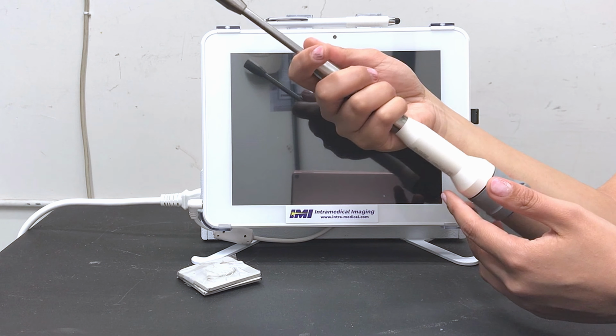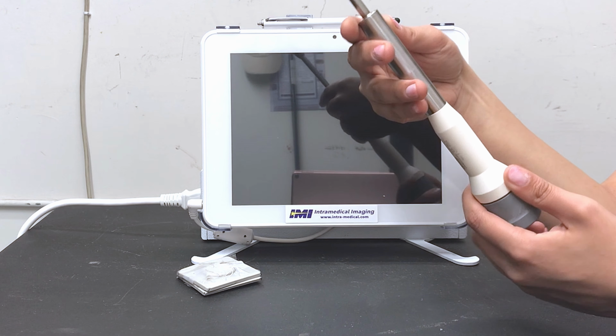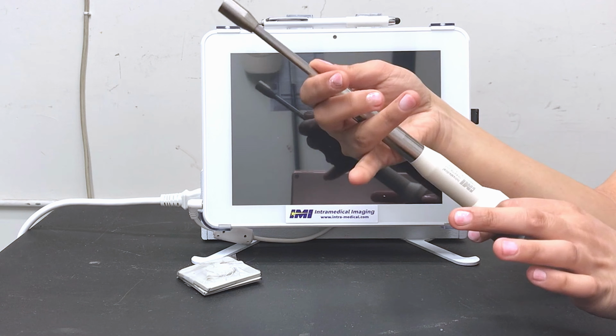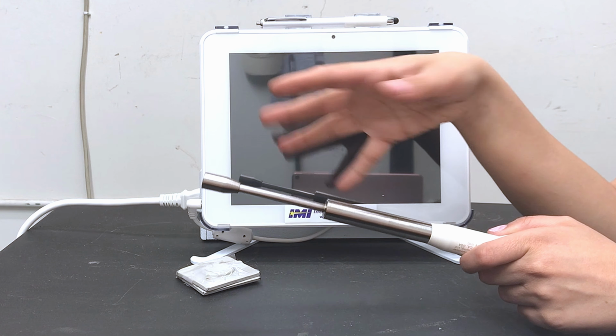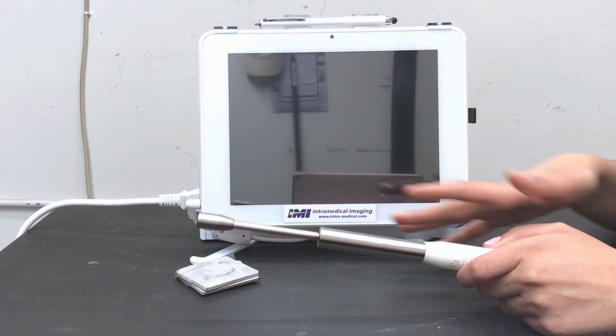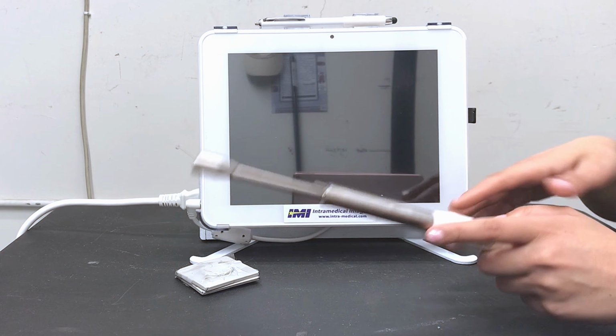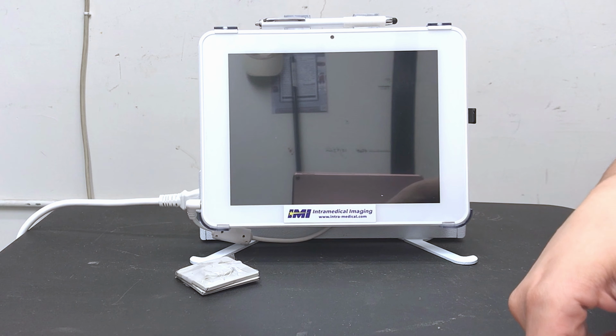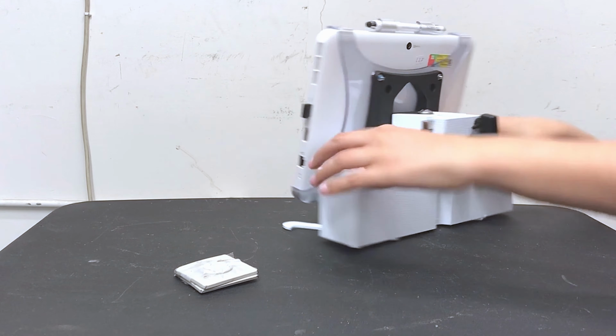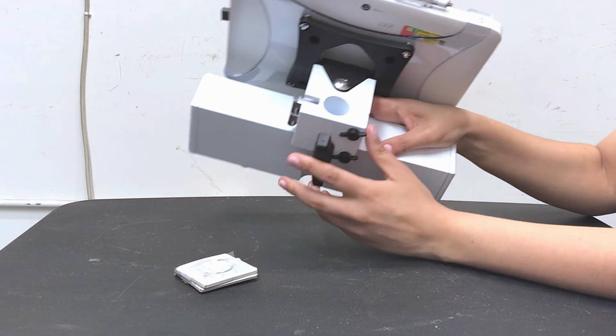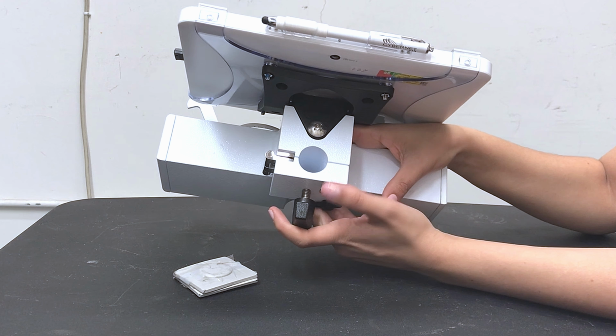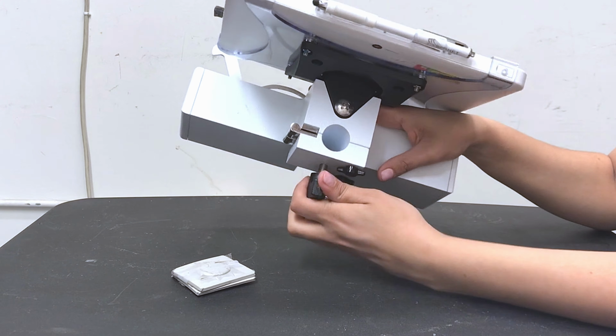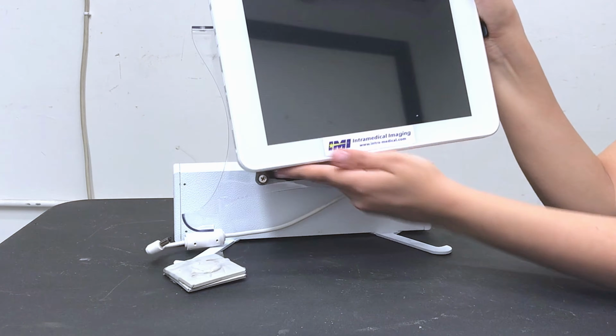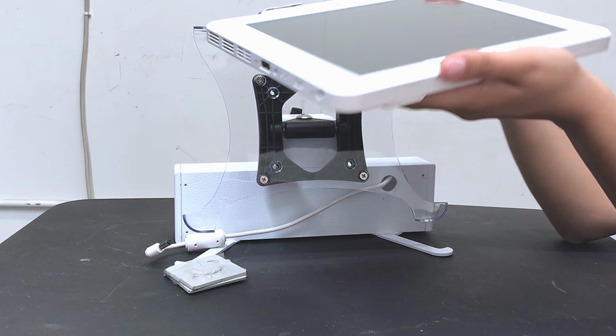Remember, the NodeSeeker Gamma probe is sterilizable through hydrogen peroxide methods like STERRAD or STERIS, but not autoclave. After removing from a sterile jacket, clean manually with a SaniWipe or ethanol and a paper towel. The control unit monitors have a 9-hour battery life and can be placed on a pole with a thumb screw for stability, sit tabletop, or be placed in a sterile jacket for use in sterile areas.